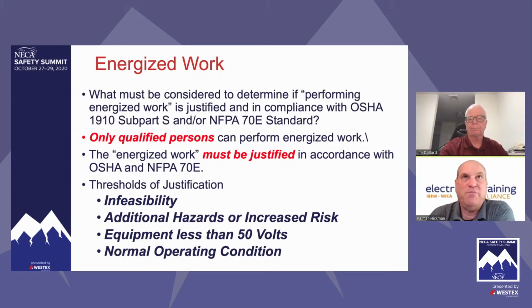You thought the arc flash boundary was going to be, let's say, 2 feet. But because of this delayed opening time, due to lack of maintenance, now the arc flash boundary is 10 feet. So people you thought were outside the boundary, wearing flammable clothes, are now involved in the arc flash event.